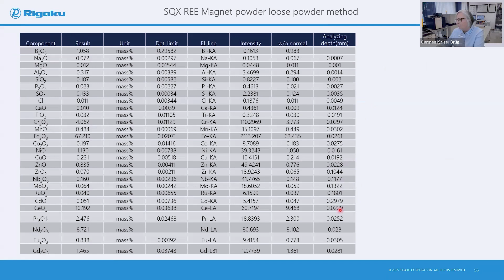Of course, our software helps you to understand this. Originally, we had some examples here to see the analyzing depth. The fundamental parameters module in our software will calculate the thickness that's needed. But in general, if you have enough powder, it is better to have a sample that is infinitely thick. Our aim with pressed powder is always to get 4 millimeters thick pressed powder. But if you don't have enough, then we could try to use this kind of cell.